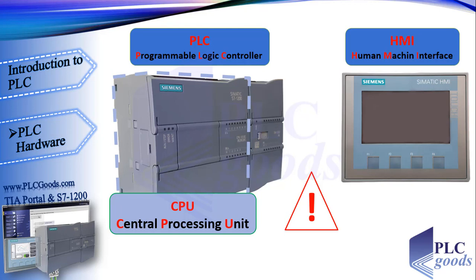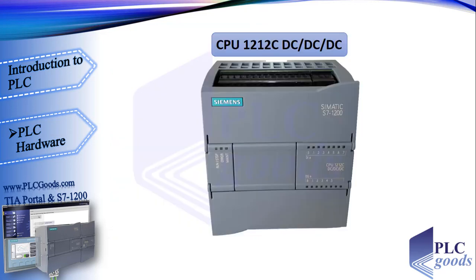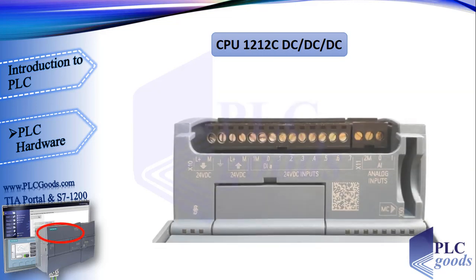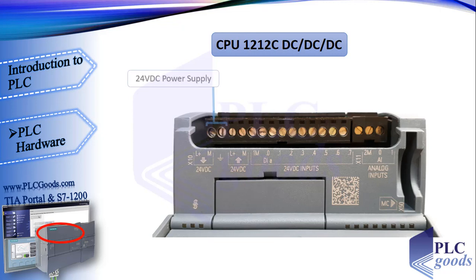Let's start with the CPU. In this course we'll use a CPU S7-1200 from Siemens. The SIMATIC S7-1200 controllers are classified into five categories; in this tutorial the S7-1200 1214C model will be used. Behind the top door cover there are terminals: the first two terminals connect to an external 24-volt DC power supply. Some models require 120 or 220 volt AC, distinguished by the word 'AC' in the model name — be careful, because connecting the wrong supply will immediately damage the PLC.